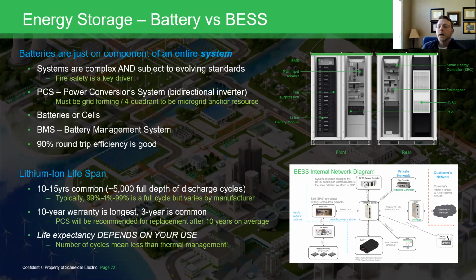They typically come with around a 3-year warranty as standard, but you can often purchase options for a 10-year warranty. Currently, 10 years is about the longest you're going to see out in the market. That's typically because the power conversion system has a mean time rate of failure around 10 years as well, so these things kind of coincide with one another. Does that really mean your inverter is going to fail after 10 years? Probably not, but you're taking a risk after that point.